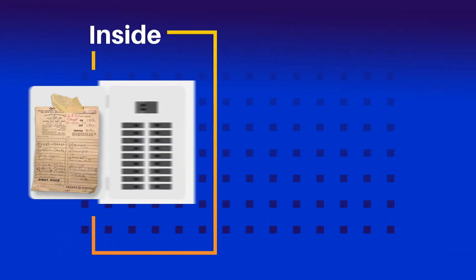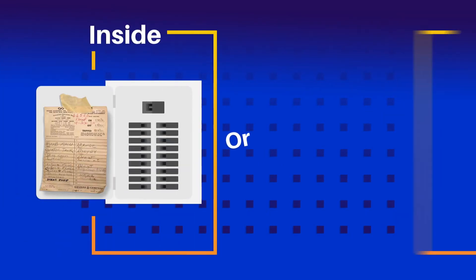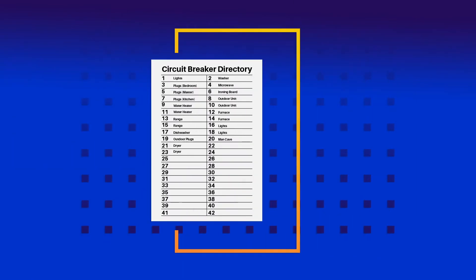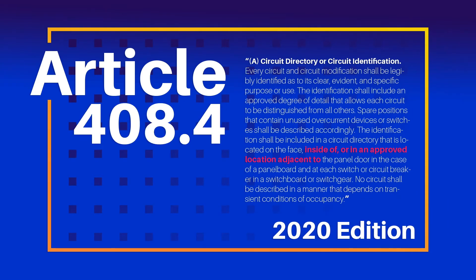Historically, panel directories were found on the inside of the door or attached to the front of the panel. Usually, directories are a template supplied with a panel board from the manufacturer. But those templates often only have a small space for the written description of the load being served. The 2020 NEC adds language that allows for the panel directory to be in an approved location adjacent to the panel board.